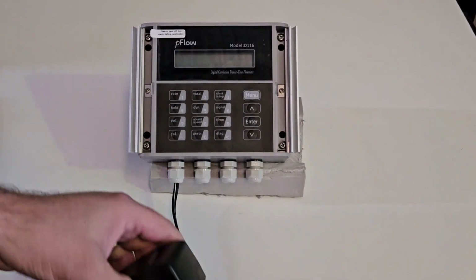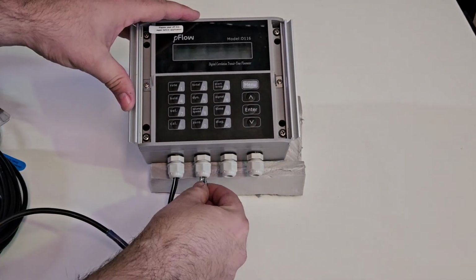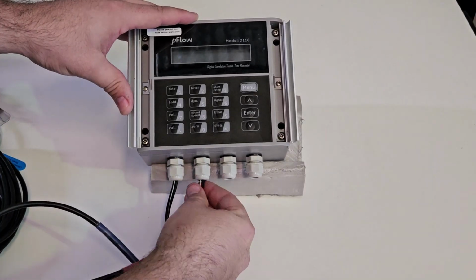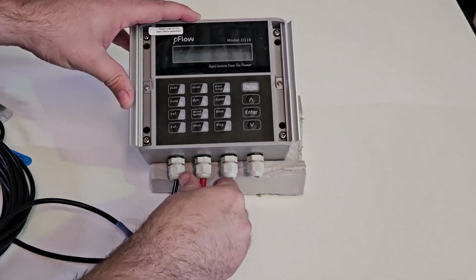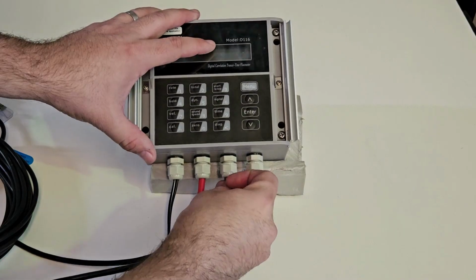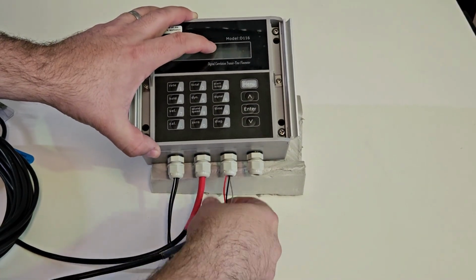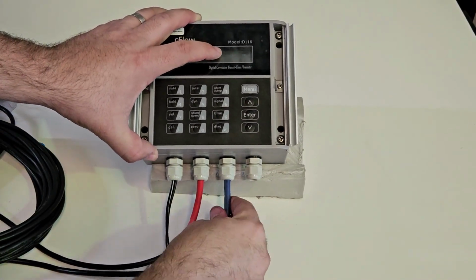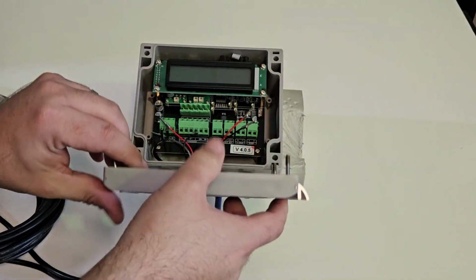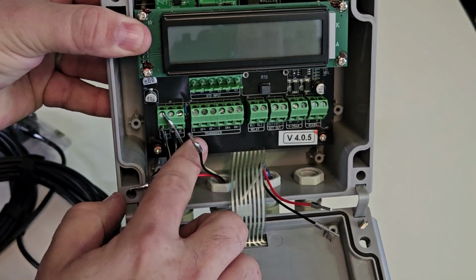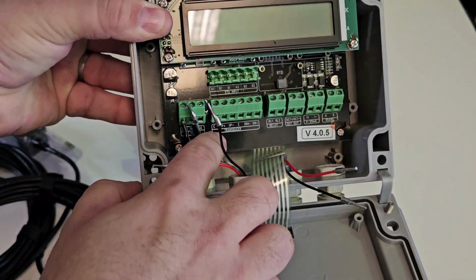Loosen off the glands. Then insert this upstream cable into the second cable gland, as it's best aligned with the upstream cable ports. Then you can take the downstream cable and do the same. Feed it through the cable gland next to it. Reopen the case. Here you can see on the board the marking where transducer cables are installed.